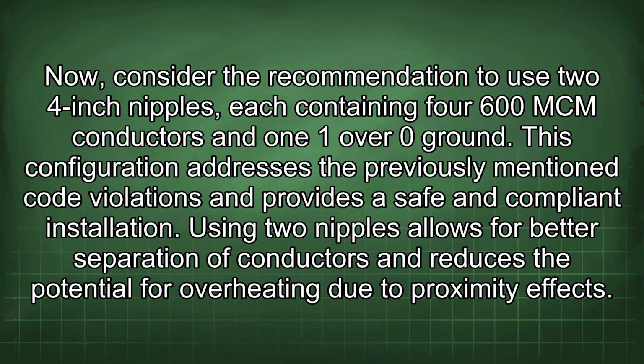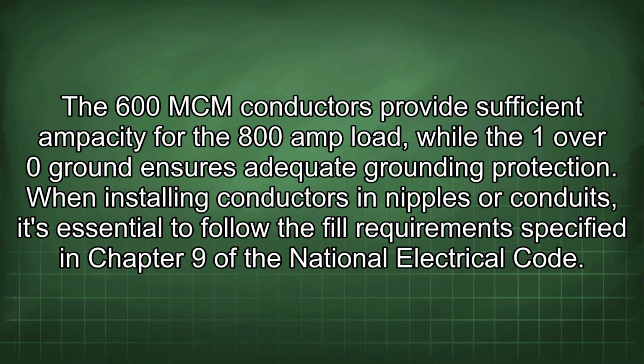Now, consider the recommendation to use 2 4-inch nipples, each containing 4 600 MCM conductors and 1 1/0 ground. This configuration addresses the previously mentioned code violations and provides a safe and compliant installation. Using 2 nipples allows for better separation of conductors and reduces the potential for overheating due to proximity effects. The 600 MCM conductors provide sufficient ampacity for the 800 amp load, while the 1/0 ground ensures adequate grounding protection.